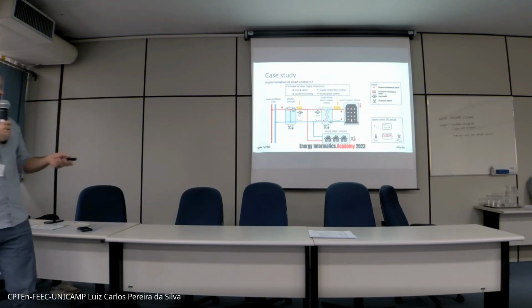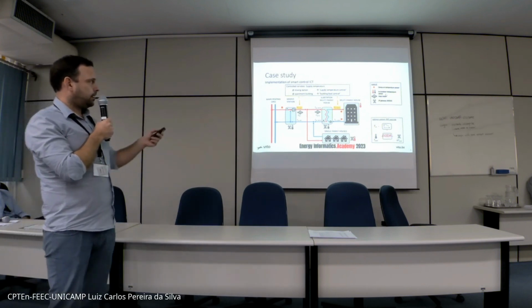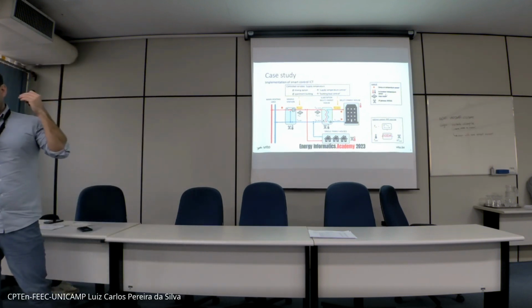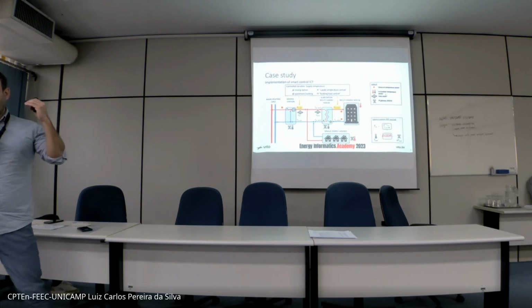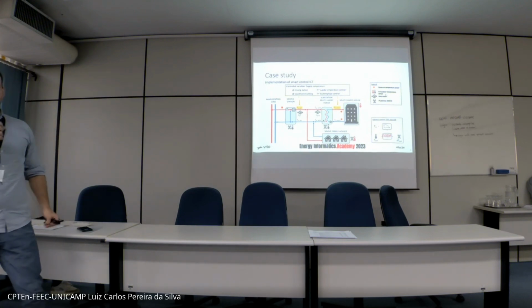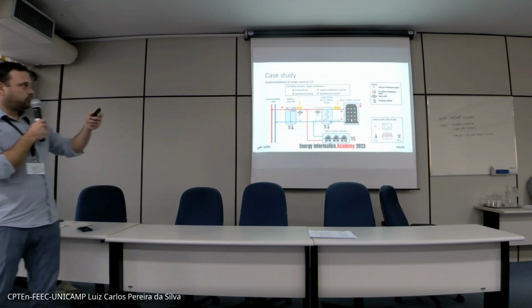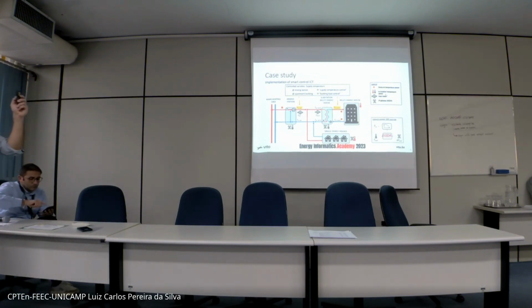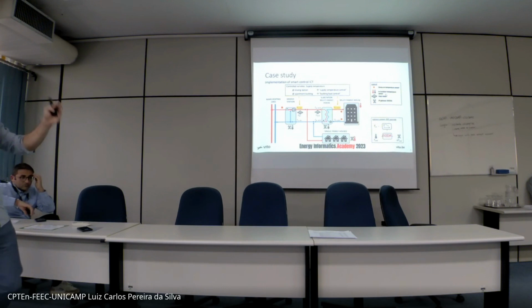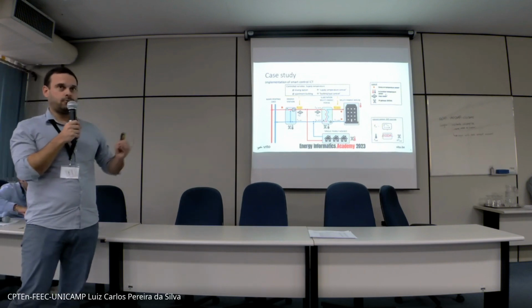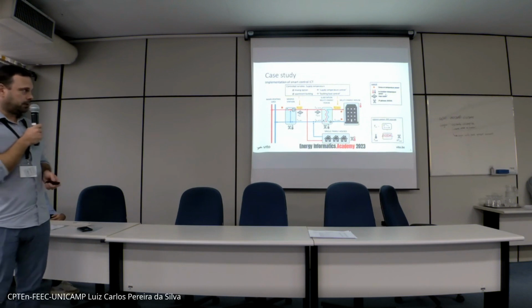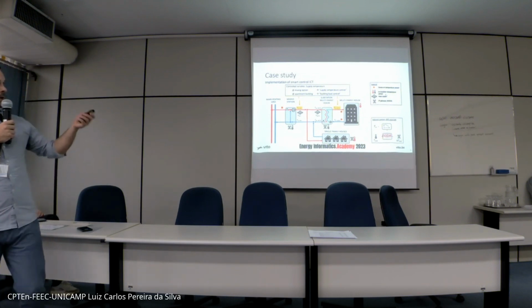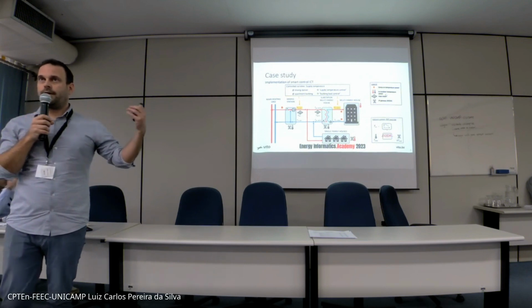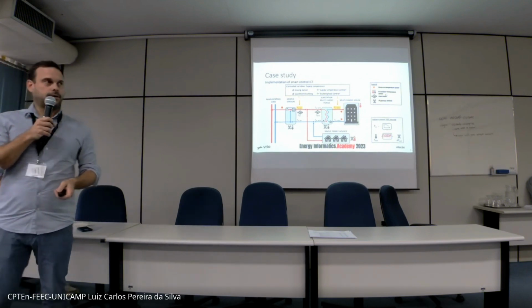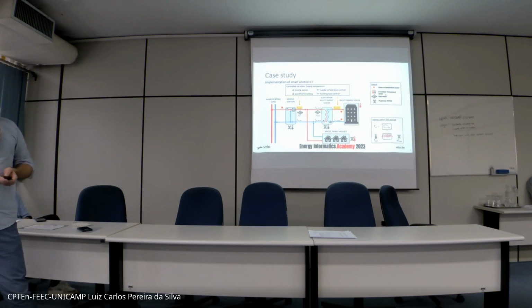There we can control the temperature of the water going into this pipe network. Then we have the substation in the multifamily house, and there we were able to control the set point of the supply water going into the heating system. So there are 2 controlled variables. We can control the temperature of the water going into the network, and we can also control the temperature of the water going into the indoor heating circuit of this apartment building. And how it's done is that we override the typical heating curve control set point. So it's very easy to do actually.